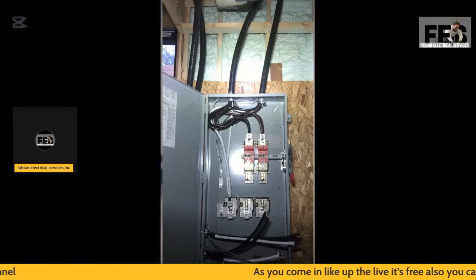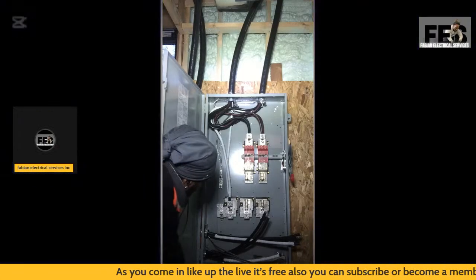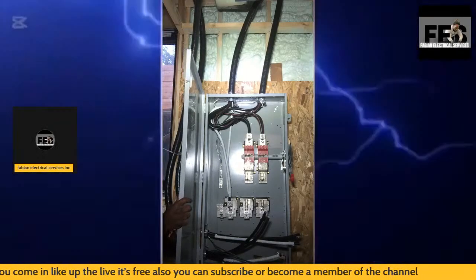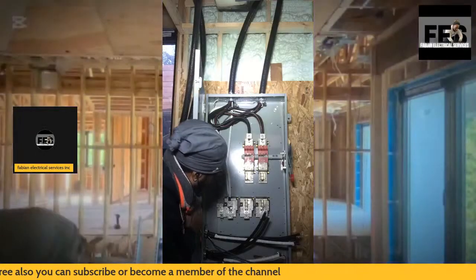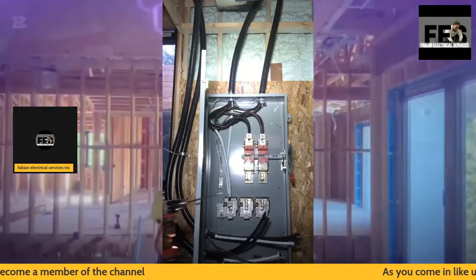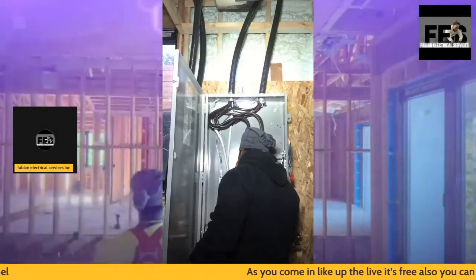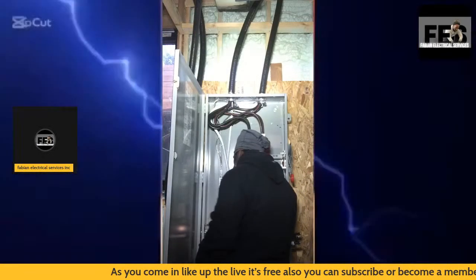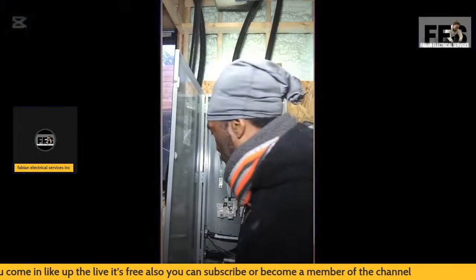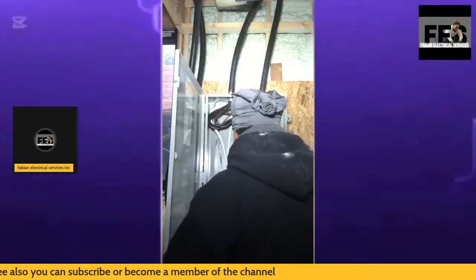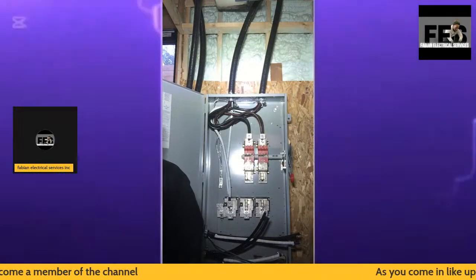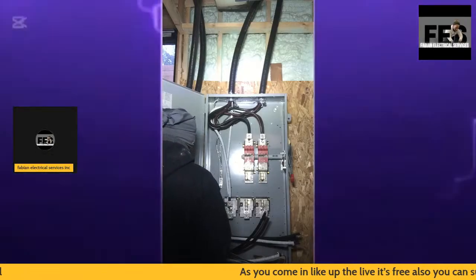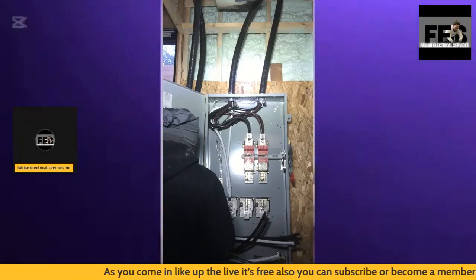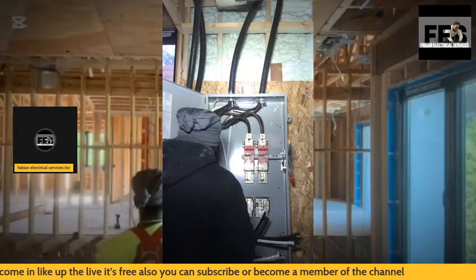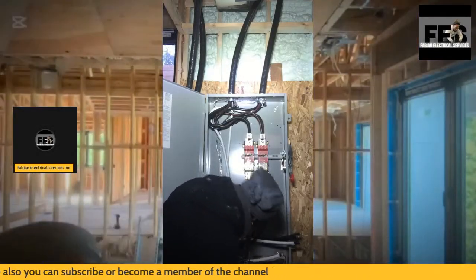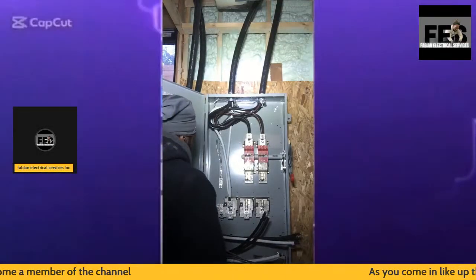What we have here is basically a 400 amp electrical installation of the disconnect. When it comes to the disconnect, it's a heavy duty service, and you have to use the proper bolts when installing this. As you can see, I have 2x4s placed on the back here, so I've strengthened the back side of the installation for the 400 amp disconnect.